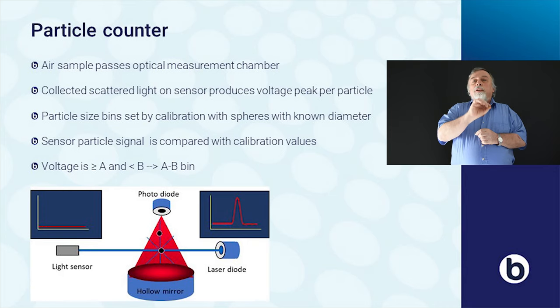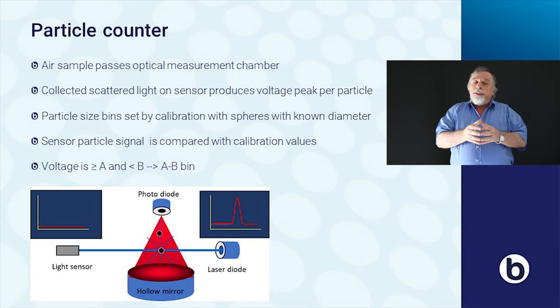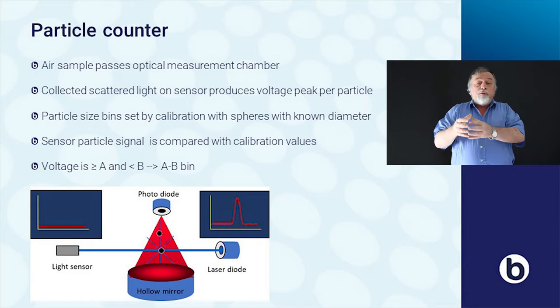Normally a particle counter is calibrated for a number of particle sizes. When you're measuring, the particles are just put into particle size bins — particles between size A and B, particles between size B and C, and so on. This distribution we get we call a differential distribution, and later I will explain how you can make a cumulative distribution of this.